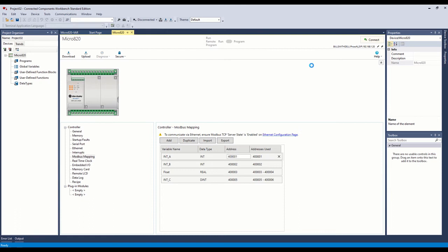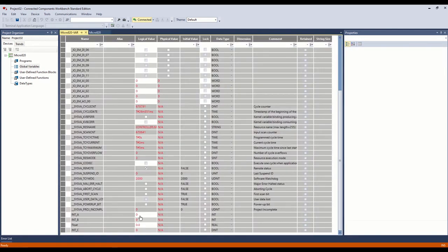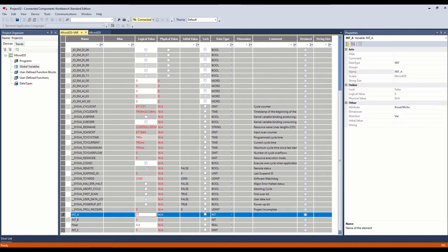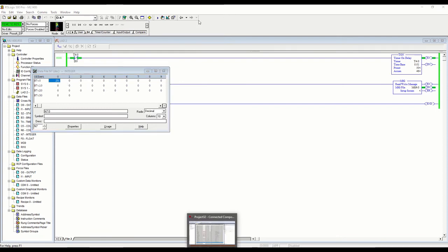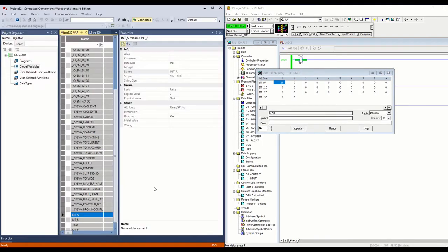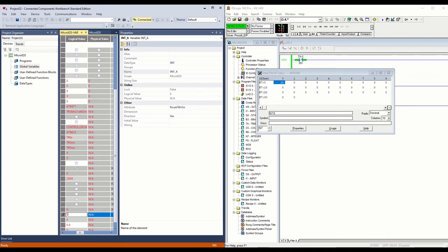Just a second to connect to this controller. Okay, here we are connected — we'll open up the values and we have a zero in here. We're going to put a value of 25 in here and we should see that value update over here. There we go — we know we're reading that register. If we change the value to 50 over here, we should see it change to 50 on the right side. Correct — you saw this value update, so we know we're reading that value correctly.